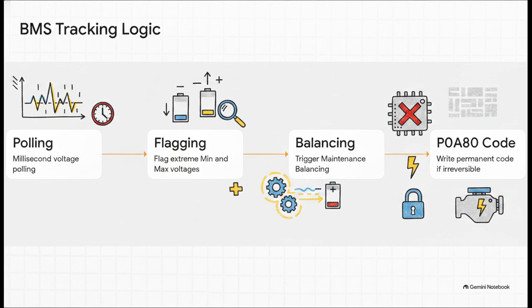Every few milliseconds, the analog front-end chip polls the voltage of every single cell, looking for a very specific damning pattern. If a cell is flagged as having the lowest voltage when discharging, meaning it's the fastest to run out of energy, and then when you plug the car in, it's flagged as having the highest voltage because its capacity is so tiny it fills up instantly, the BMS zeroes right in. It catches the cell acting as both the fastest to empty and the fastest to fill. To be absolutely sure, it triggers a maintenance balancing routine to try and heal it.